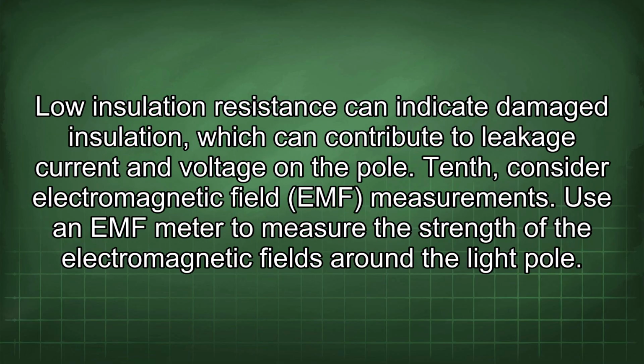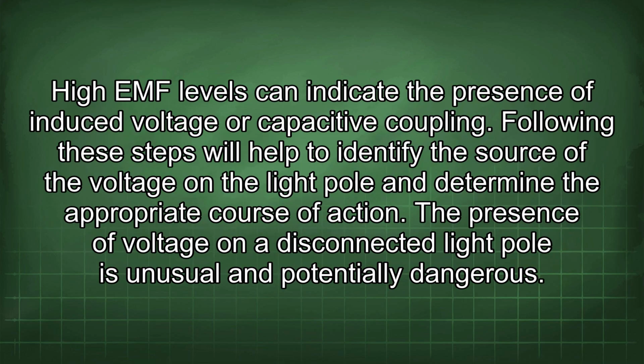Low insulation resistance can indicate damaged insulation, which can contribute to leakage current and voltage on the pole. 10th, consider electromagnetic field (EMF) measurements. Use an EMF meter to measure the strength of the electromagnetic fields around the light pole. High EMF levels can indicate the presence of induced voltage or capacitive coupling.